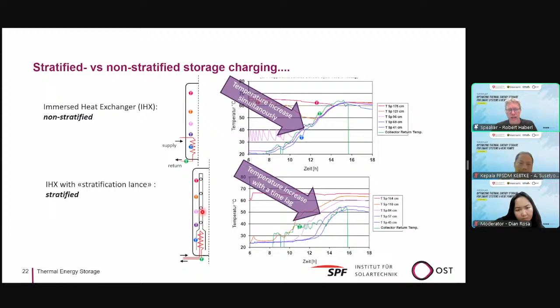It's the same for a heat pump. If you want to heat it with a heat pump and the return temperature or the lower temperature increases, the efficiency will drop. In the next case, you again have the immersed heat exchanger, but that time you have a stratification lance, meaning the water is captured and forced to rise in that lance, and it can escape on the holes on the side, on the part where the density of the water is the same as the density of the heated water. And here you have a temperature increase with a time lag, meaning it rises on the top of the storage tank first, then in the second position and the third position, and only last on the bottom. And that allows the return temperature to keep low a long time. That allows to heat the storage tank to a useful temperature quite early, and increases therefore the exergy content of the storage tank and the efficiency of the overall system.